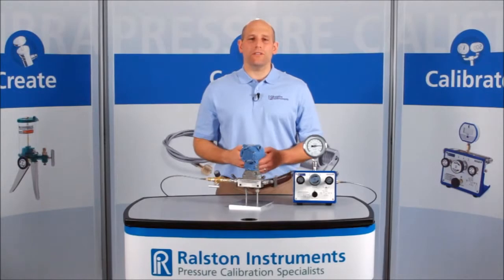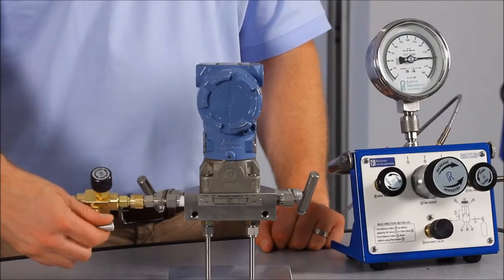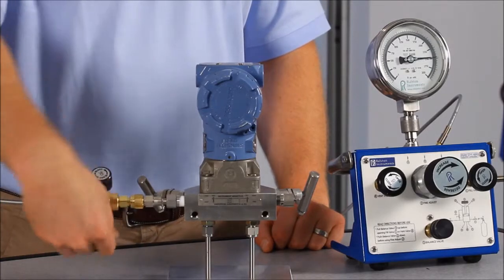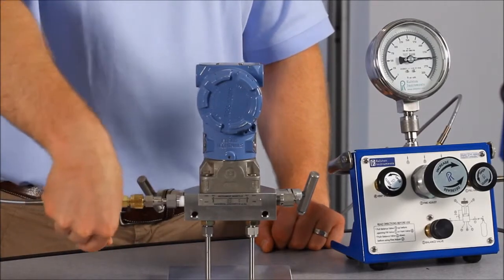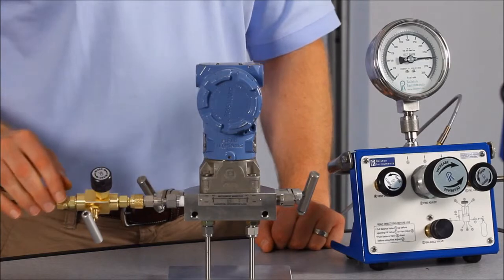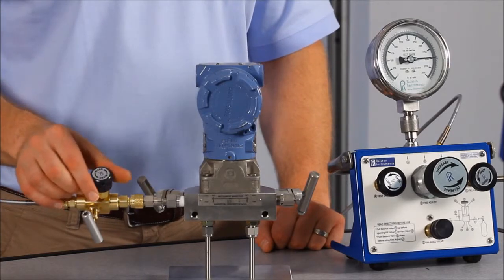When you're done testing this device, you can simply close the isolation valve to block your pressure source from the device under test. Then open the vent valve to release the pressure between the isolation valve and the device under test.